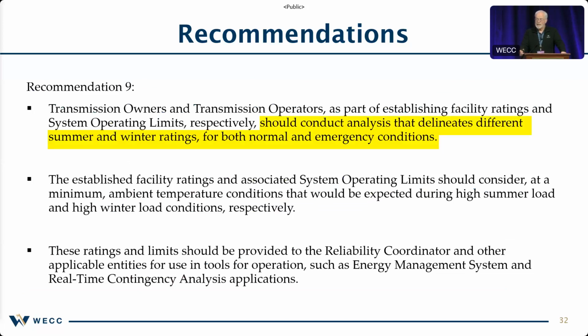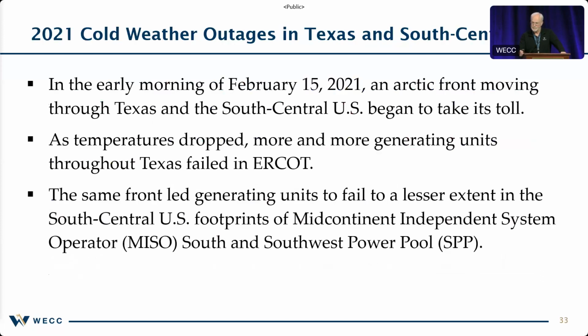And another recommendation, recommendation 9, talks about that the transmission owners and operators should conduct an analysis that delineates different summer and winter ratings for both normal and emergency conditions. So we know that FERC put out Order 881 talking about ambient adjusted ratings. It was identified in this event and in others that congestion across the transmission system may have been caused by the fact that they were using static winter ratings rather than dynamic winter ratings, and entities that were using more dynamic winter ratings were able to allow more power to flow than those that weren't.